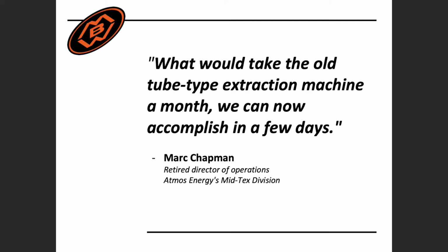Now, I do not want to make any promises on how fast or slow an extraction will be for these reasons. We do not know how much gas has migrated underground. Different soil conditions and caps play a major role in this process. We do not know if there are multiple leaks. Every leak is different and unpredictable. Some leaks you may find quicker than others that may have been going for longer periods of time. The V.E.U. is not a miracle worker, but it gets the job done the most efficient and fastest way possible. Having realistic expectations with the V.E.U. is important, but when compared to the old Venturi method, it is substantially better.